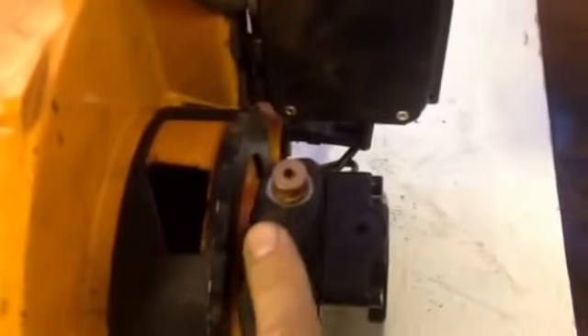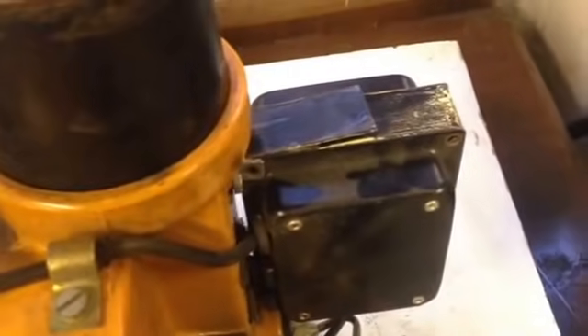That is the on-off for the oil supply, a little solenoid. That is a transformer that produces 30,000-odd volts to produce a spark. There is a little magic eye here - oops, it's just fallen apart, I took it out - but that is there so it knows whether the flame is actually lit or not. Okay, and then you've got your control box.